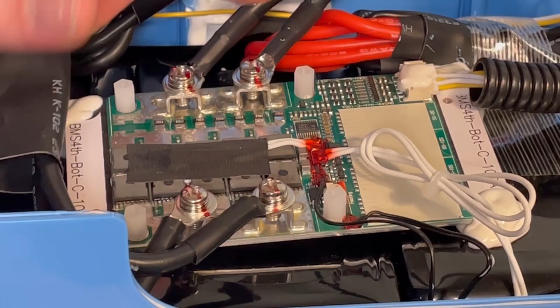Okay, so these appear to be 2, 4, 6, 8, 10 Mosfets here that control the charge and discharge cutoff functions. All your power is going to flow from the battery through these and into your wires here. It appears that there is a temperature sensor of sorts up on top, but I'm not sure if it's a temperature sensor or if it's like a circuit breaker. It's so big. I don't want to take this one off the BMS because that's stuck down with tape, but when I get in here, I want to take this one out. I'll see if there's a part number on there. I'm gonna go ahead and start taking this apart a little bit more.